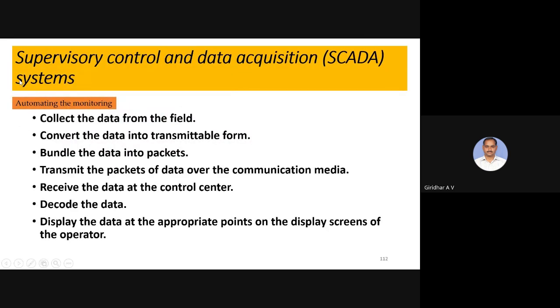So from these SCADA systems, you can collect the data from the field, convert the data into transmittable form, bundle the data into packets, transmit the packets over the communication media, receive the data at the control centers, decode the data, and display the data. In that way, we are using different communications and media, like power line communication, satellite communication, or very high frequency radio communications, passing into the master stations.